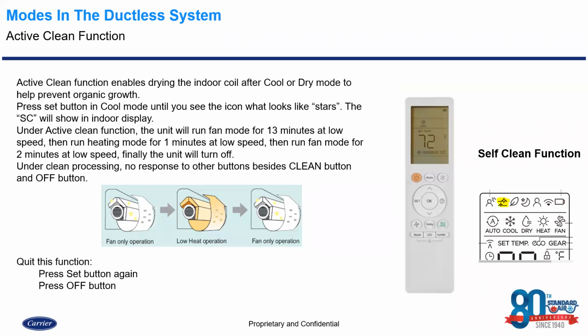Next mode we're going to talk about is our self-clean function. Okay, so on this, just like we did with the prior 2 modes, we're going to go ahead and hit the set button on there. And what we're going to be looking for is the two little stars with lines through them that kind of indicate something shining, like something's been cleaned. Okay, once you see that icon, which you see right here below the self-clean function description, you're going to point the wireless controller at the indoor unit, hit the OK button to send that command to the indoor unit, and listen for the audible beep. Once that audible beep is confirmed, you're going to see an SC for self-clean displayed on the high wall style units. Now, if you don't have a digital display, this isn't going to come up.